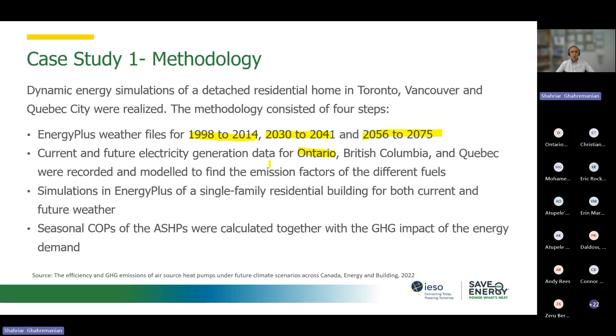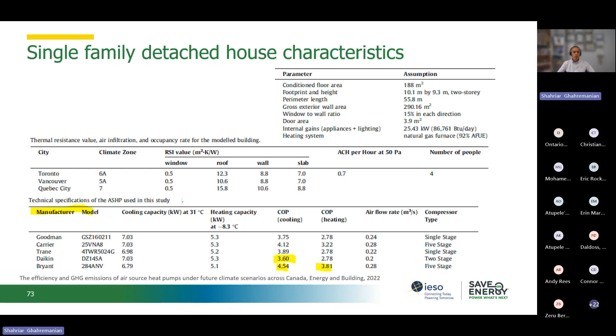They also looked at actual heat pump equipment available in the market and their COP. Look at this brand, for example, not saying it's the best, but just to show the difference in COP. We have a range of about 3.6 up to 4.4 for cooling. For heating, the typical COP is around 2.78, and it can go up to 3.8. So these are the actual equipment available in the market.